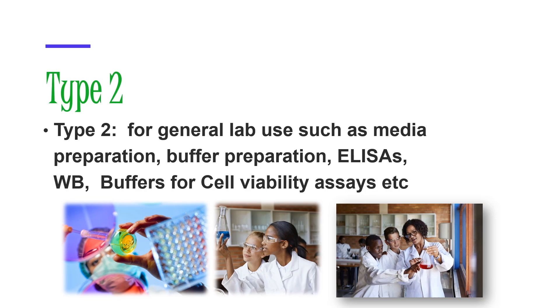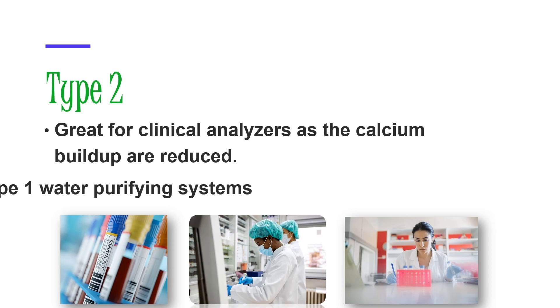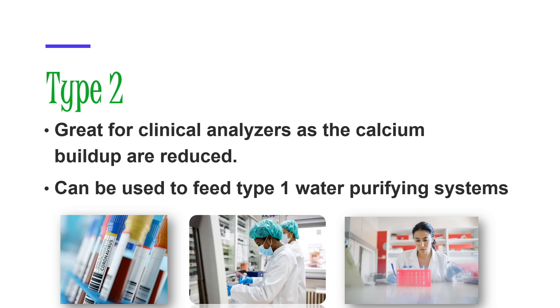The next type is referred to as Type 2 water, or Elix water. This is for general lab use — making media, making buffers, diluting for ELISAs, western blots, or cell viability assays. You can get away with Type 2 water. Type 2 water is also great for clinical analyzers because it reduces calcium buildup, so the water won't gunk up your instruments.